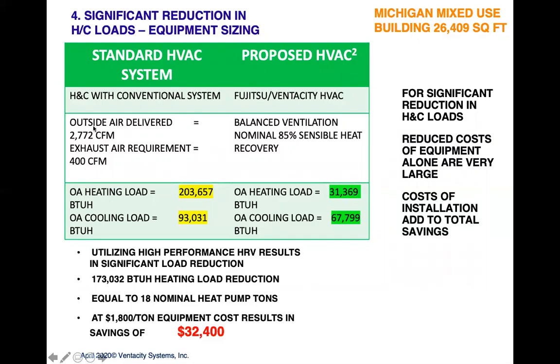here the outside air is 2,700 CFM required. Exhaust was only 400, but if you're doing it balanced, we're looking at almost 2,800 CFM. At design temperature in Michigan, where this project is located, we were looking at a heating load of 203,000. In other words, bringing in 2,800 CFM and having to heat that air up to room temperature was 203,000 BTUs in the winter, 93,000 in the summer for cooling.